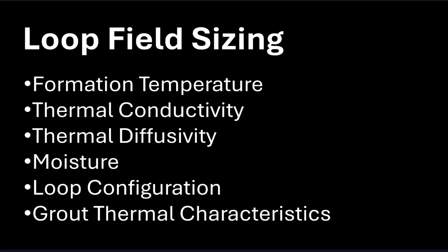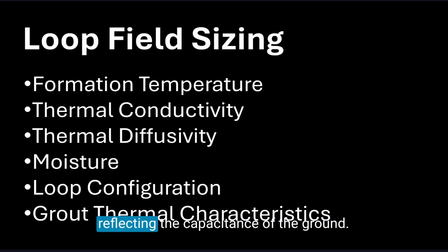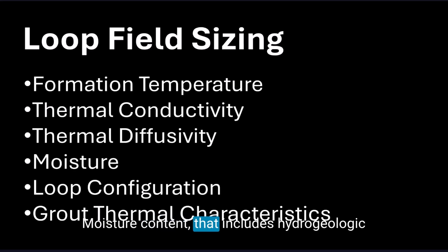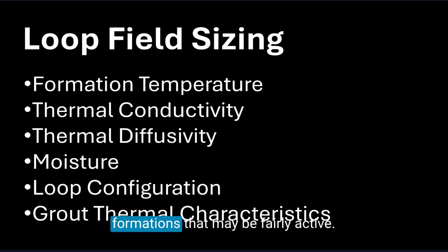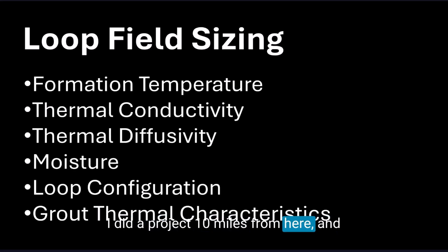aware of that. The thermal conductivity, the ability of the soil to conduct heat. The other characteristic, which is very important, is thermal diffusivity, really reflecting the capacitance of the ground. Moisture content, that includes hydrogeologic formations that may be fairly active. I did a project 10 miles from here, and at 286 feet down, we hit a 6-foot void, which was actually an underground river. That could have a tremendous impact on how well that loop field actually works.